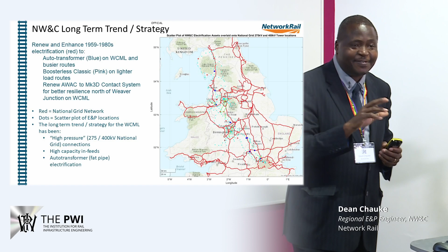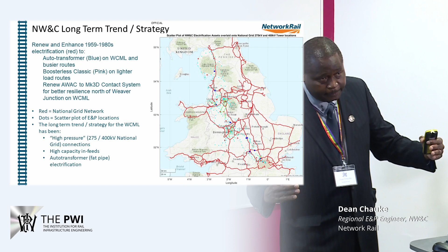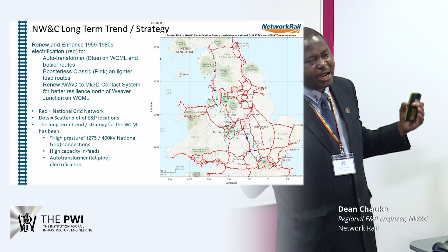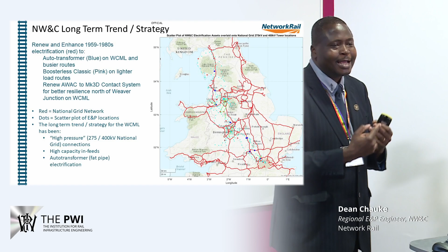For the Northwest, we're at the Mark III system with AWAC, the aluminum conductor reinforced with steel. It's showing significant signs of wear. Part of the problem with the pressurized system is that we increase the fault level to 12 kA instead of 6 kA, meaning we push more energy into the system, and therefore have to upgrade all the overhead line conductors and the strings that connect the substations.